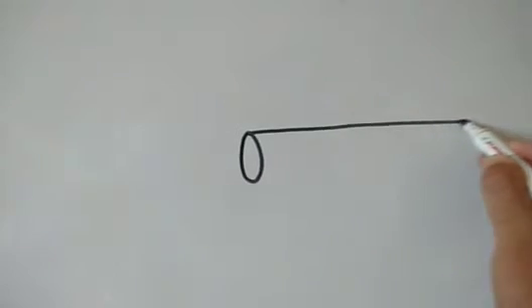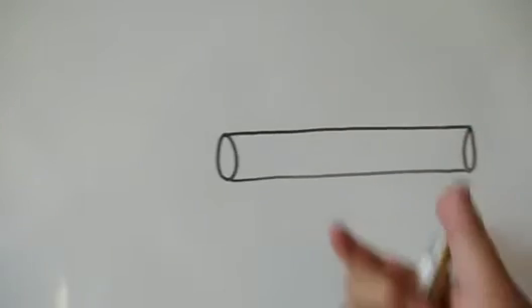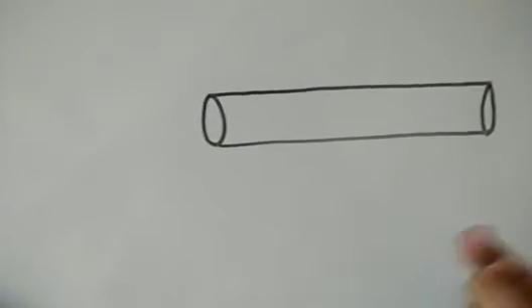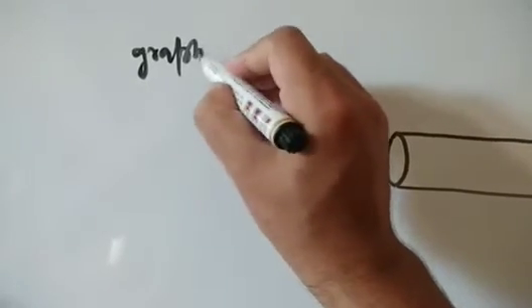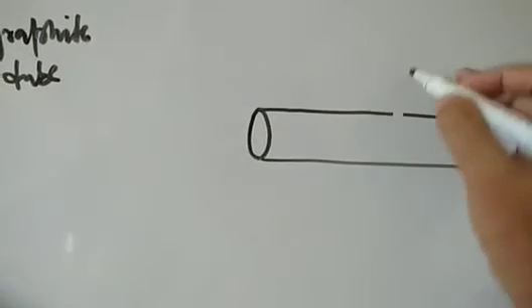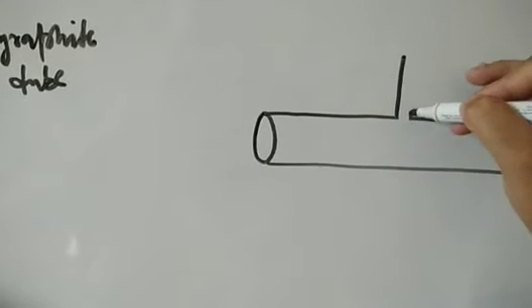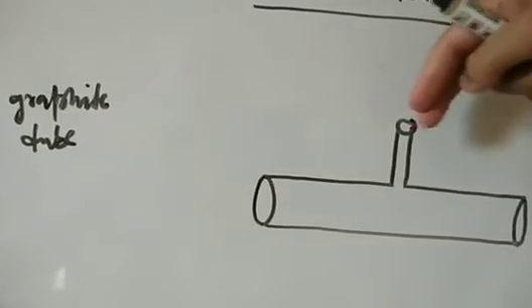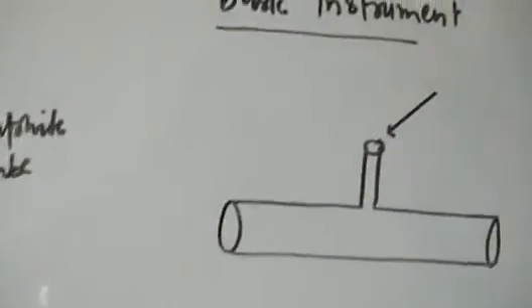The main component is a graphite tube — it's a long graphite tube. Graphite is a carbon material. It is hollow at both ends, and at the middle point there is an opening for sample injection. The sample, in the form of small droplets or mist from the nebulizer, is introduced through this opening.